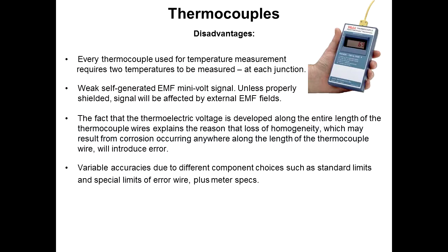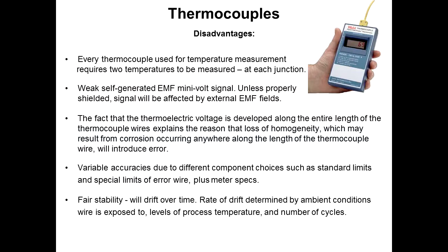Different accuracies will vary. There's standard limits of error wire and special limits of error wire, plus meter specs. We'll get into that a little bit more in a few minutes. They're fairly stable. They drift over time. There's an entire industry out there of what's called thermocouple recalibration equipment. Once a thermocouple probe is made, you cannot recalibrate it. What you're doing is, as it drifts, building an offset into the meter for the error. So you constantly have to read the error and then make allowances for it in the meter on thermocouples.